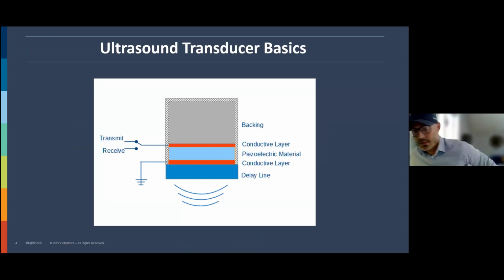So to dig into the technology here, or the basics, I've put on some ultrasound transducer basics here. I'm sure some of you are familiar with ultrasound, but this is how an ultrasound element works. So you use ultrasound to send into your material, and then it is reflected, and then you use this reflection signal to determine whether there's a damage or not. So a transducer element consists of a piezoelectric material in the middle, and that's the secret sauce here. So the piezoelectric material vibrates when it's put under voltage pressure, and also vibrates when it detects mechanical stress, which is a sound wave, for example.